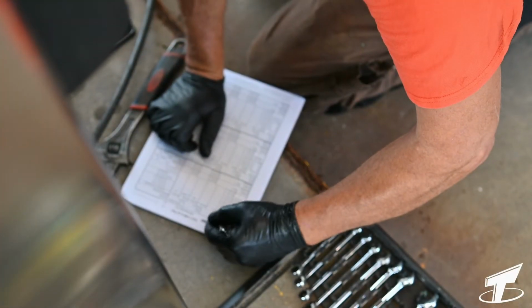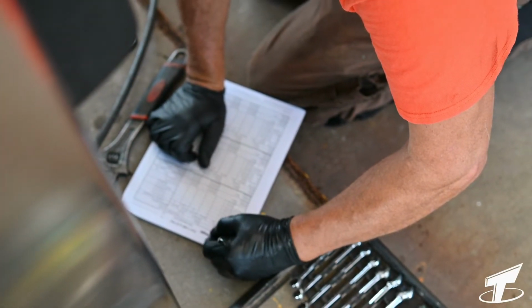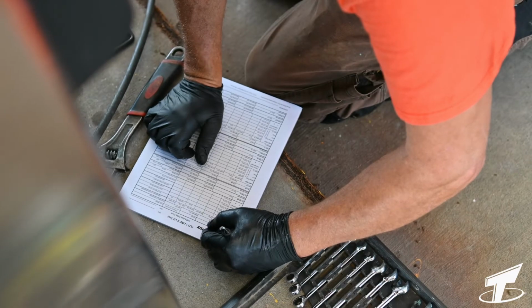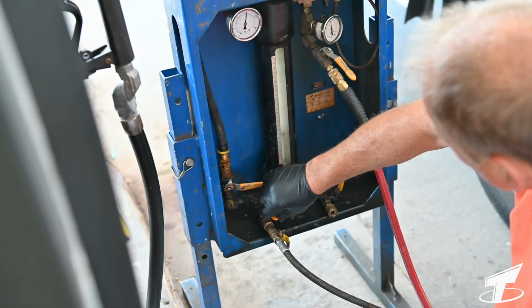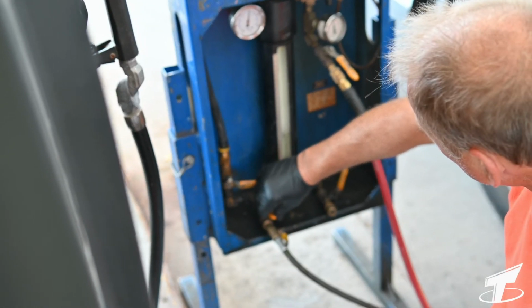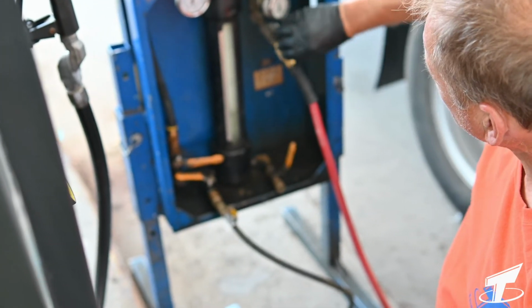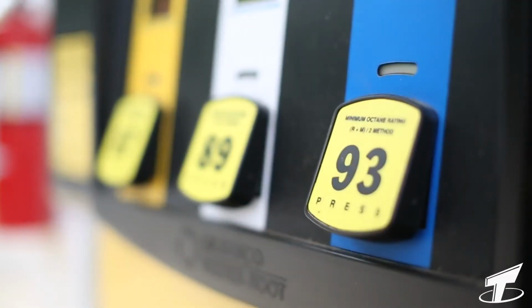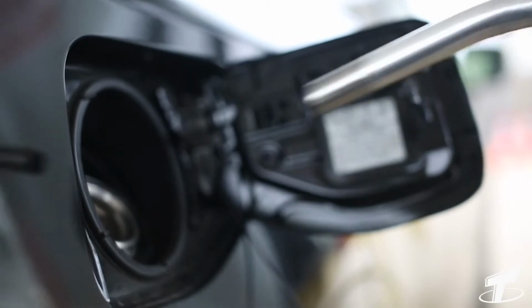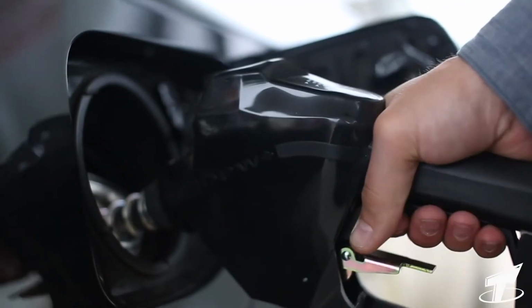Product lines are tested using hydrostatic pressure. Our technician calculates the volumetric leak rate and determines if the lines meet the current line testing criteria. Leak detectors may be tested as installed in the piping system. Neither line tests nor leak detector tests add to the system downtime since they are performed simultaneously with the tank test.